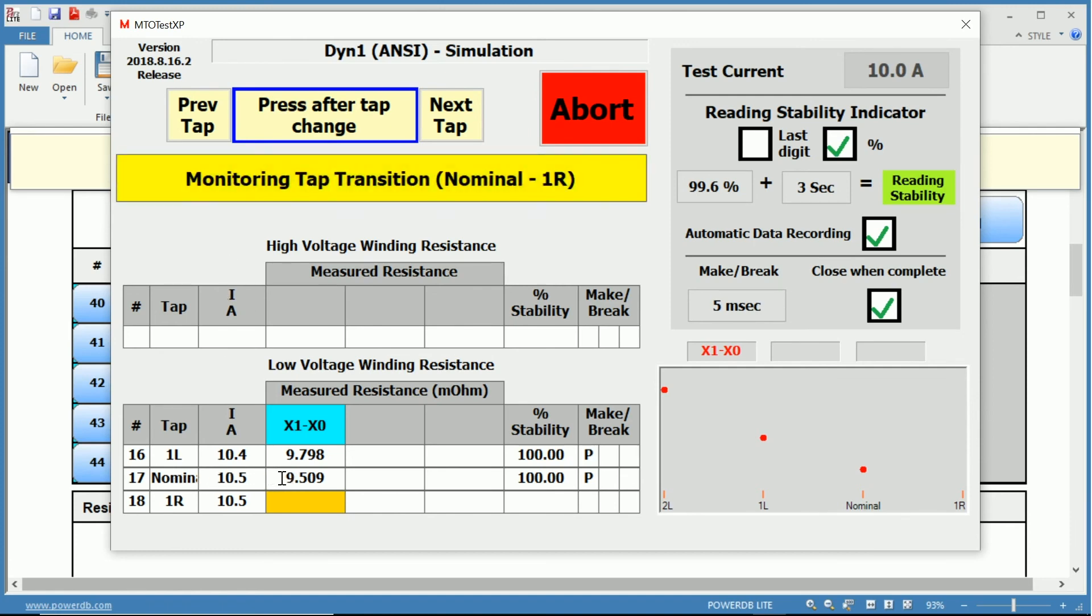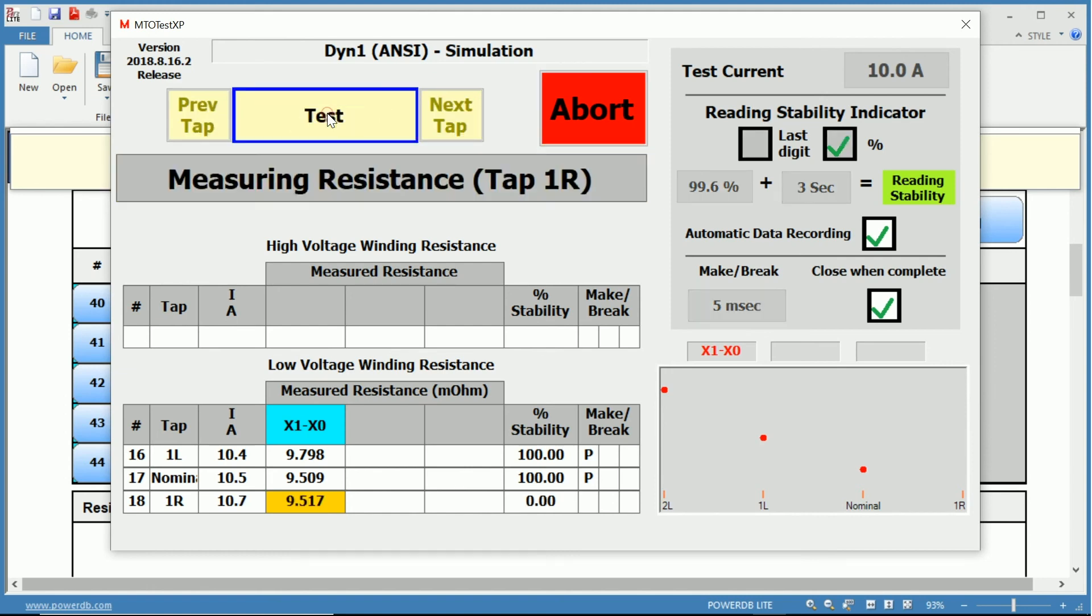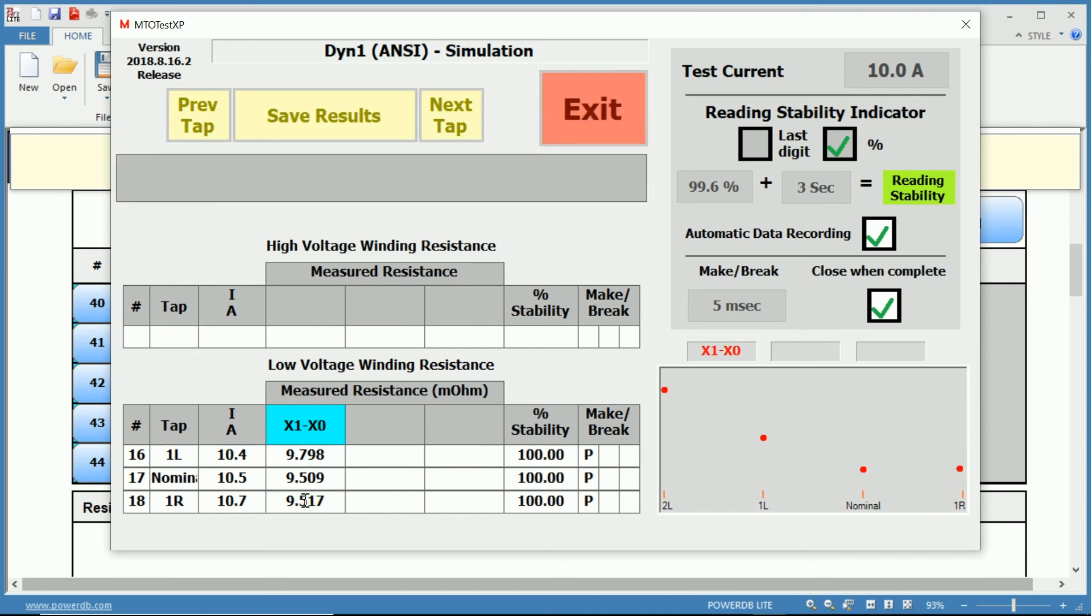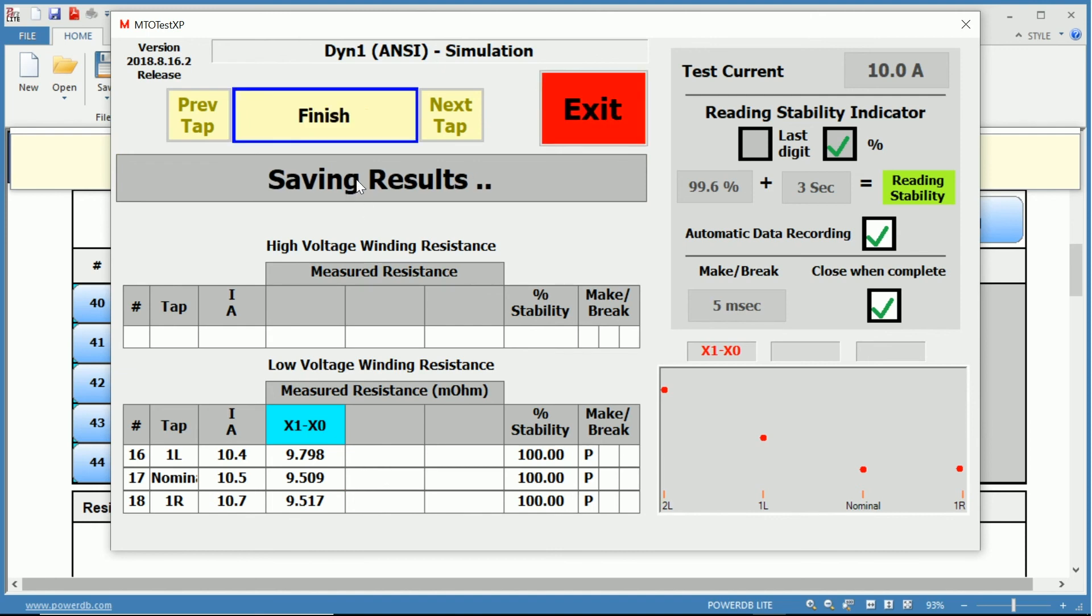We have completed our nominal tap resistance, so 10.5 amps, 9.509 milliohms, and we've passed each one of our make-before-break conditions. It's still monitoring the tap position from nominal to one raise. Change the tap. We press after checking, after we change the tap.